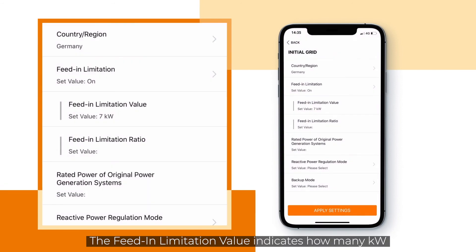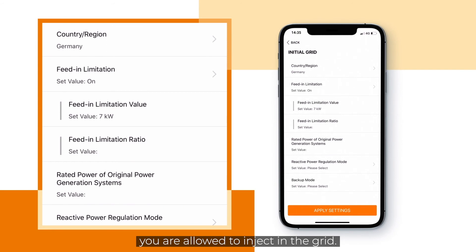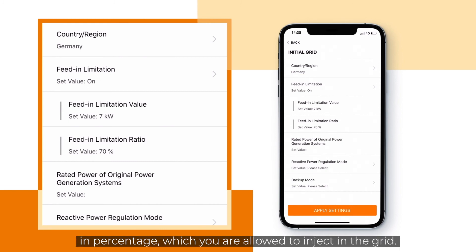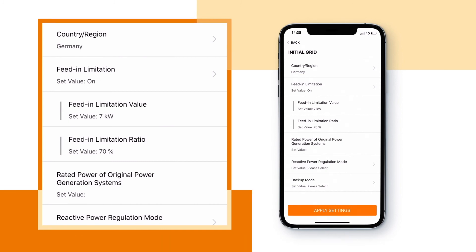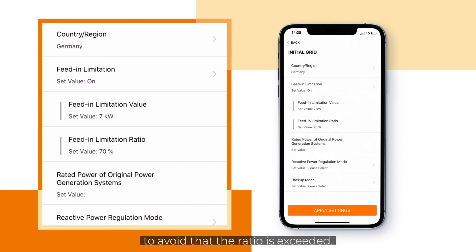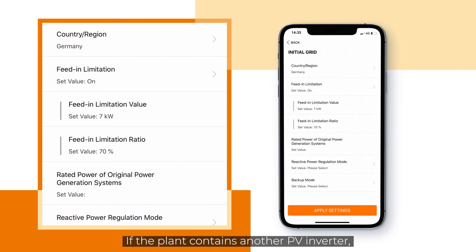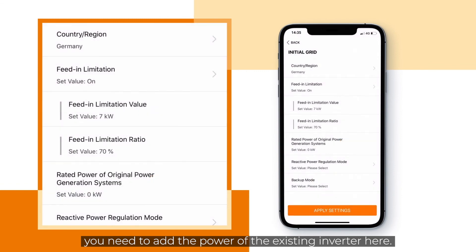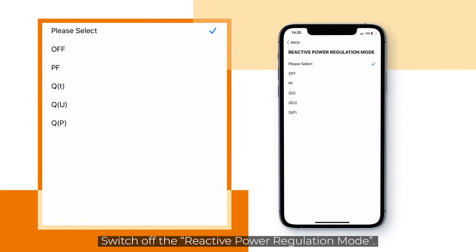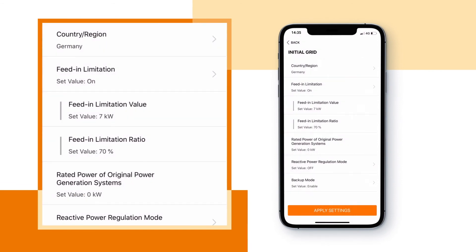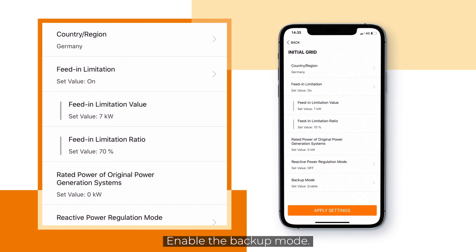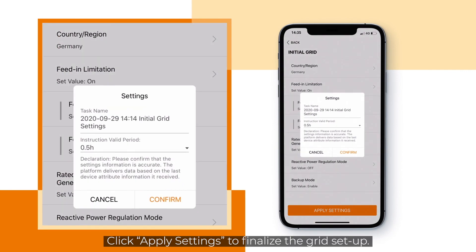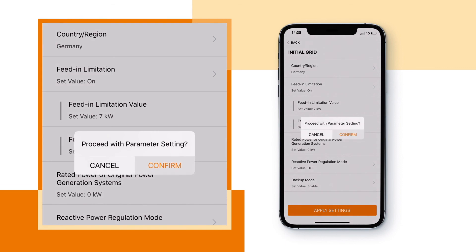The feed-in limitation value indicates how many kilowatts you are allowed to inject into the grid. The feed-in limitation ratio states the amount of the installed power in percentage which you are allowed to inject into the grid. The inverter will be able to limit its output power to avoid that the ratio is exceeded. If the plant contains another PV inverter, you need to add the power of the existing inverter here. Switch off the reactive power regulation mode and enable the backup mode. Click apply settings to finalize the grid setup. Click confirm, and once more.